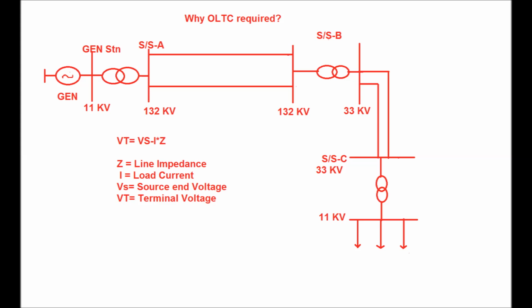So there are two types of tap changer. One is the on load tap changer and another is the off load tap changer. In case of the on load tap changer, there is no requirement of shutdown of the transformer. The tap position can be changed remotely in online mode. But in case of the offload tap changer, we have to take a shutdown of the transformer and then the tap position can be changed. Normally in distribution substations there exists an offload tap changer, and in grid substations there exists an on-load tap changer, that is, for 10 MVA and higher rating transformers.